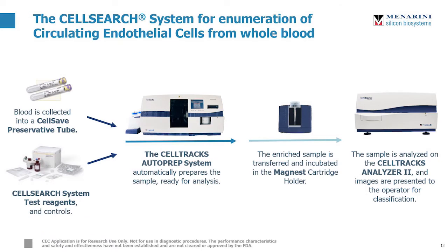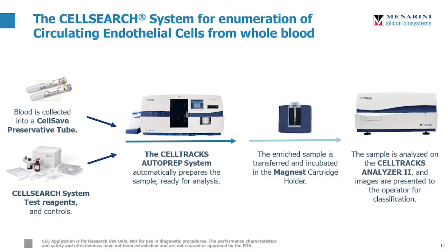To use the CellSearch system, blood is first collected into CellSave preservative tubes, which stabilize cells for up to 72 hours at room temperature. After sample prep and centrifugation, cells are loaded onto the CellTracks AutoPrep system, which automatically prepares the sample. Endothelial cells are enriched using anti-CD146 ferrofluid nanoparticles and further stained for easy identification. The enriched sample is then transferred and incubated in the MagNest cartridge holder, which uses a magnet to pull the cells onto a single plane where they can be analyzed on the CellTracks Analyzer.